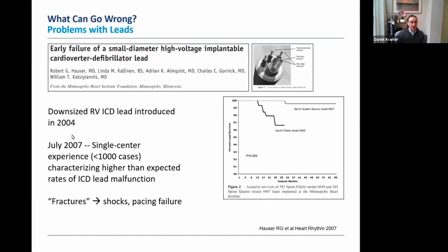So just a few years after they started using this device clinically, they amalgamated their experience and identified a strikingly deviant failure rate for this model, called the Sprint Fidelis, compared to the workhorse lead from that same manufacturer that they had been using at the time—and which, in fact, we still use now.